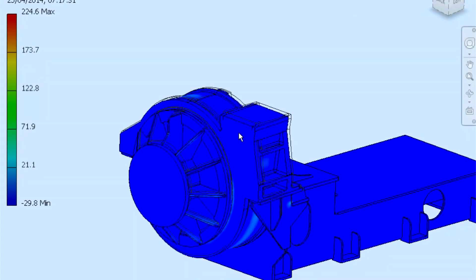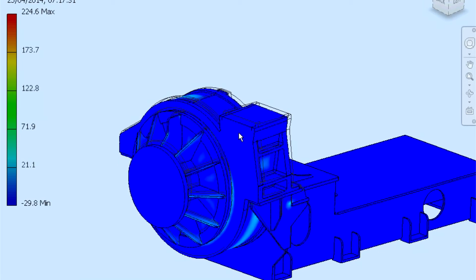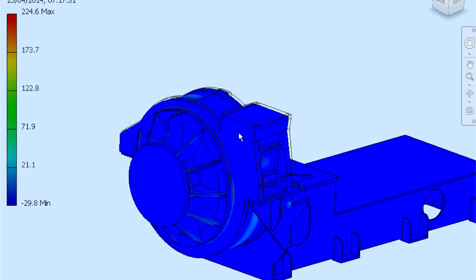In order to verify that the fan case can withstand such extreme pressures, an FEA simulation has been carried out. By creating a 3D model with actual material properties and assigning a number of boundary conditions, we can compute principal stresses generated in the casing under load.